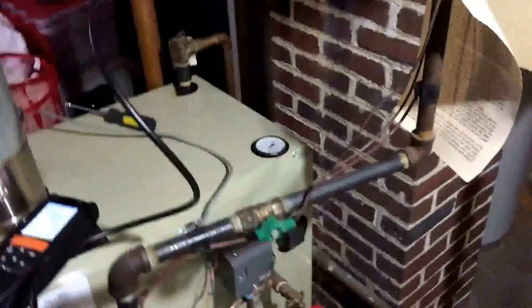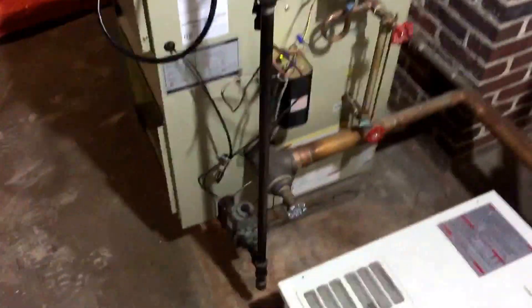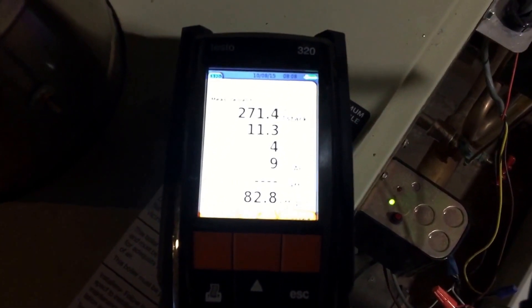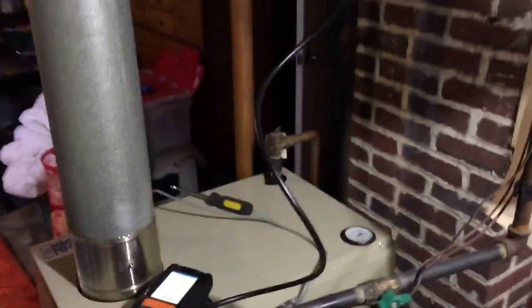I cleaned out the burner — there's no sense in filming that, everybody's seen that before. They weren't really that dirty. Not too bad. Almost 83% efficient right now.